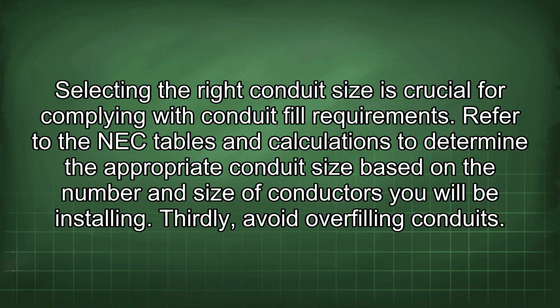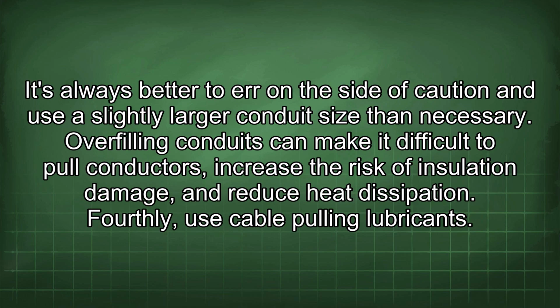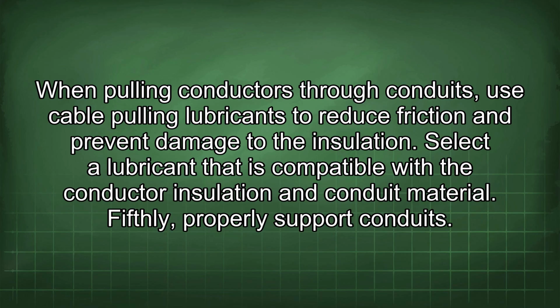Thirdly, avoid overfilling conduits. It's always better to err on the side of caution and use a slightly larger conduit size than necessary. Overfilling conduits can make it difficult to pull conductors, increase the risk of insulation damage, and reduce heat dissipation. Fourthly, use cable pulling lubricants. When pulling conductors through conduits, use cable pulling lubricants to reduce friction and prevent damage to the insulation. Select a lubricant that is compatible with the conductor insulation and conduit material.